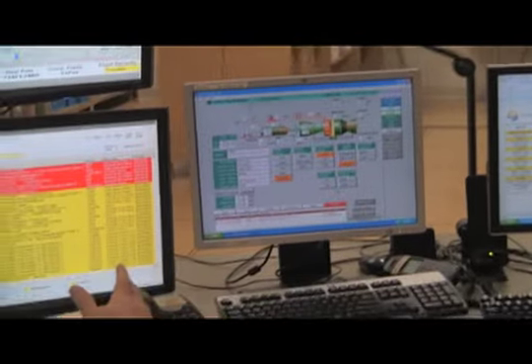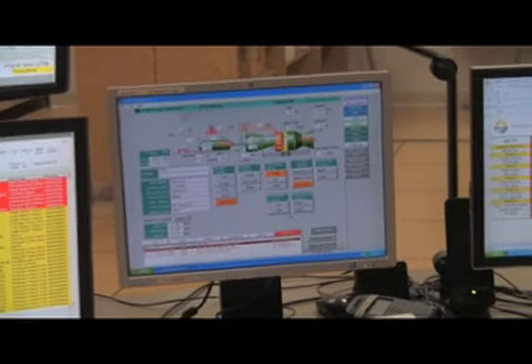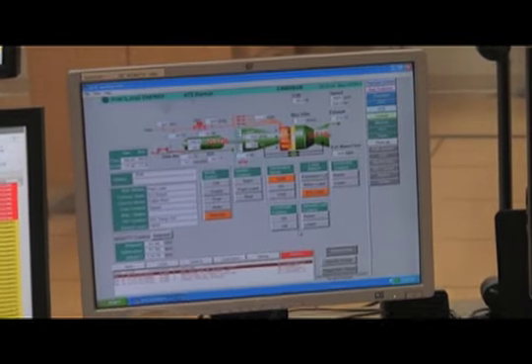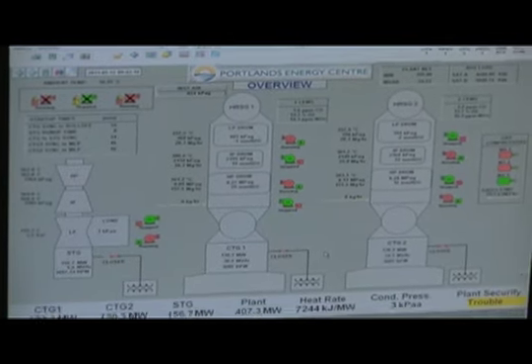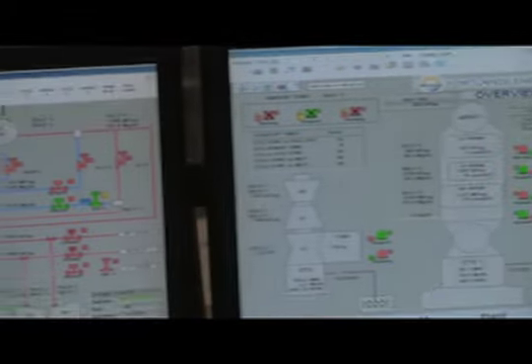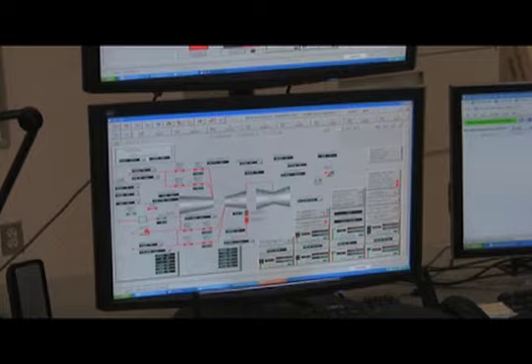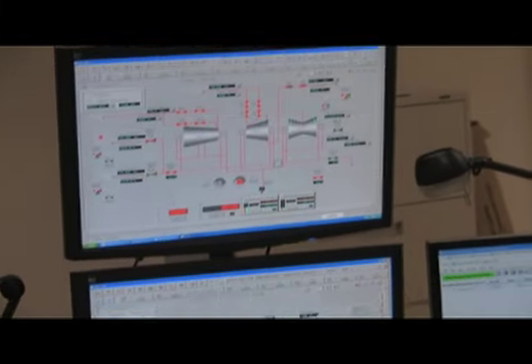Basically from here we have control of everything. This represents our gas turbines. This is our main operating system, all plant auxiliaries, which would be pumps, fans, different things. And this screen represents our steam turbine. We have the two gas turbines out there, and we have a steam turbine on the main plant here. The gas turbines feed the steam turbine steam, and it's a continuous closed loop. And all the power we're making from each unit is represented right here: Unit 1, 2, and 3.